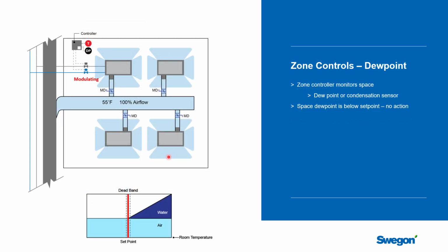So there's a bunch of different ways you can do things to help manage dew point. So let's talk about a situation right now, and what we're going to do here is look at what's going on if the space is satisfied in terms of temperature. You can see we're modulating the cooling, we're meeting the load, but we have a dew point sensor right here, and it's monitoring the space. If you are below your dew point setting, which might be 80 or 90% dew point, then there's no change. You let the system do what it would normally do and heat and cool the space as you want.